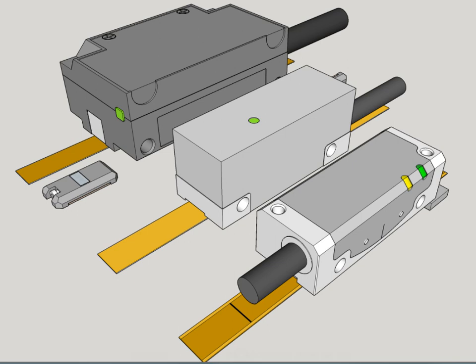Magnetic linear encoders employ either active or passive variable reluctance scales, and position may be sensed using sense coils, Hall effect, or magnetoresistive readheads. With coarser scale periods than optical encoders, typically a few hundred micrometers to several millimeters, resolutions in the order of a micrometer are the norm.